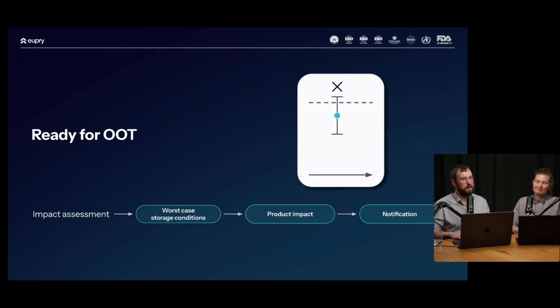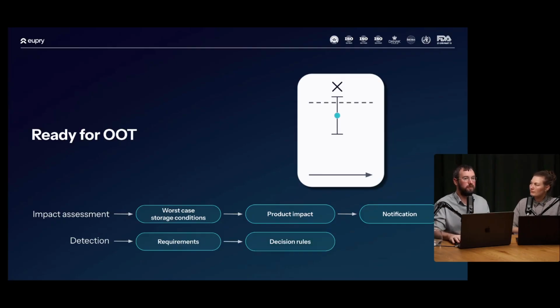A good point. And then, of course, who should you notify going forward? And secondly, what are your requirements? You need to have a good way of detecting that you're going out of tolerance. We see a lot of cases where, going back to actually being able to review the certificates, you don't know what it actually is you're looking for. So you need to ensure that you have good requirements. That also leads you to decision rules. We see a lot of companies that don't have specific decision rules for when to accept a certificate or when not to. Some laboratories will write in the MPE whether it has passed or not passed, and some laboratories will just give you results and you'll have to add them up.